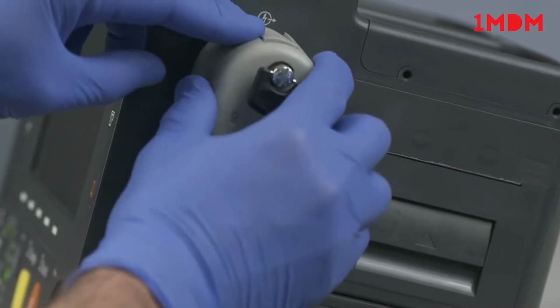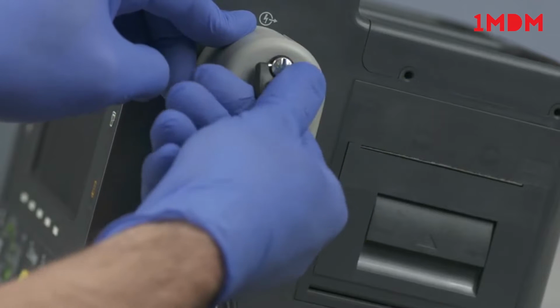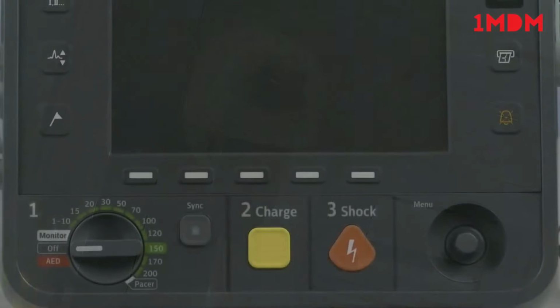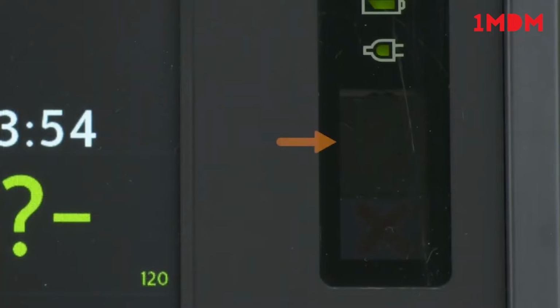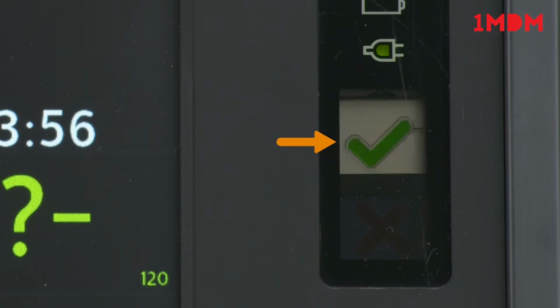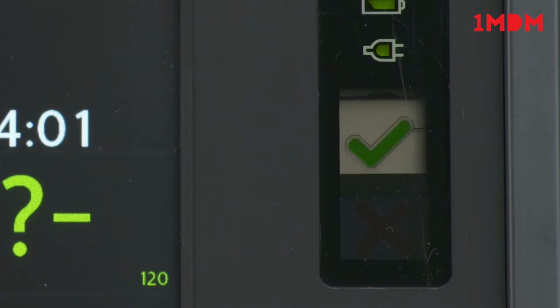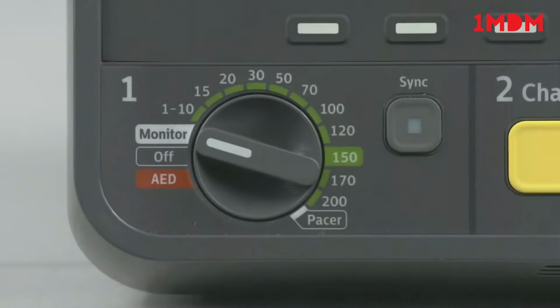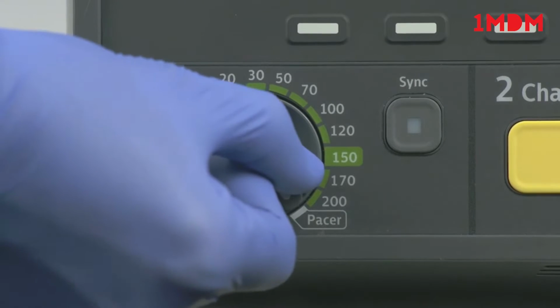If you are using the HeartStart Intrepid for transport or in high vibration environments, install the therapy cable collar that comes with your device. Operating controls and indicators are on the front. This is the Ready for Use indicator. The blinking green checkmark tells you the device is ready for use with sufficient battery power for shock, pacing, and monitoring functions. The therapy knob is the on-off switch. Just turn it to the desired mode of operation.